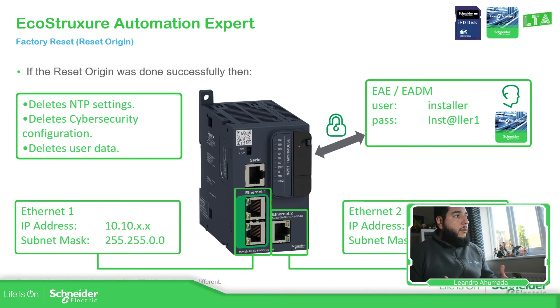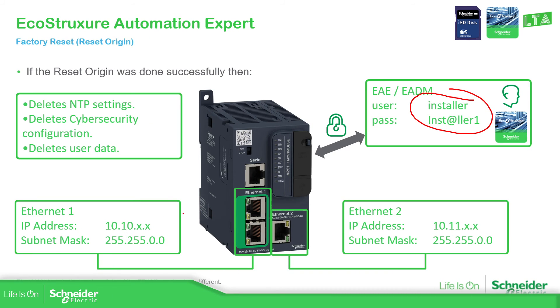Now we have done the reset. The controller by default has credentials that allow us to connect using EcoStruxure Automation Expert and also EcoStruxure Automation Device Maintenance. The default user and password are shown here. By default, the Ethernet port 1 configuration is 10.10.x.x, and the last digits are based on the last four digits of the MAC address. The same applies for Ethernet port 2 — 10.11.x.x — with subnet 255.255.0.0.